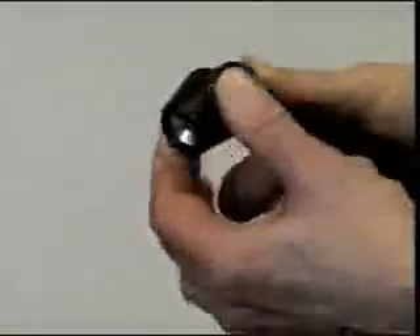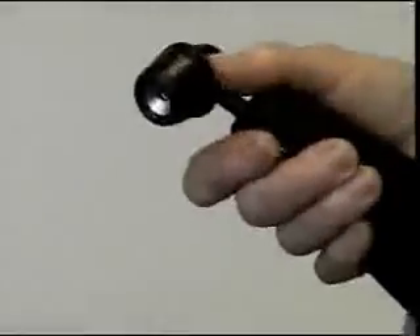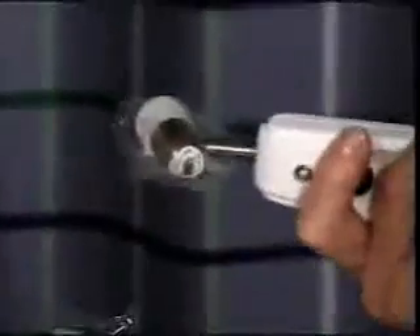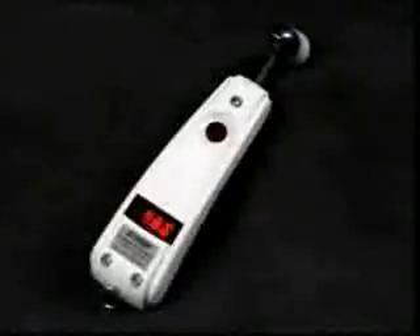The Temporal Scanner is extremely user-friendly. Just follow these simple steps. First, place a disposable cap or cover onto the probe. The disposable cap is placed on the probe by a simple push and ejected with a push of your thumb. The disposable probe cover is another option. The cover is placed on the probe by inserting the cleat at the back of the probe through the hole in the cover. Wrap the cover around the probe and place the cleat through the second hole, then simply tear the cover from the roll. Certain models can be terminally cleaned and used without disposables — contact Exergen for details.